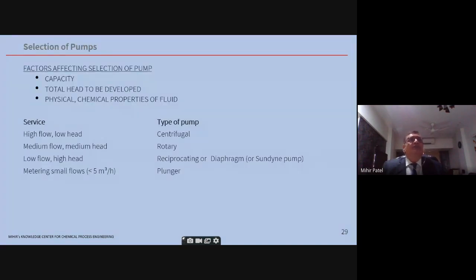Selection of pumps. Now the process engineer, while selecting pumps, has to look at a few categories: capacity, total head to be developed, and physical and chemical properties of the liquid. I have written down some services and the type of pump. This is a very brief table, but for your understanding, it's good. For high flow, low head, centrifugal pumps are good. For medium flow, medium head, rotary pumps are there. Rotary pumps basically are screw pumps, gear pumps, vane pumps. Then for low flow, high head, you have reciprocating or diaphragm pumps.